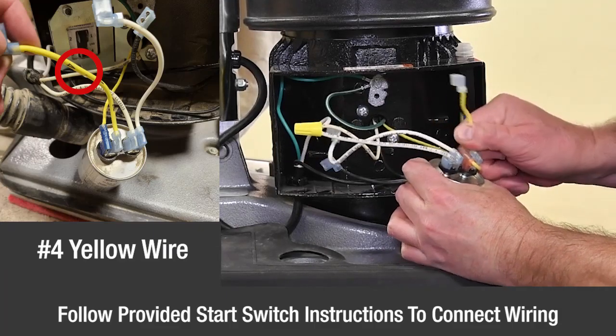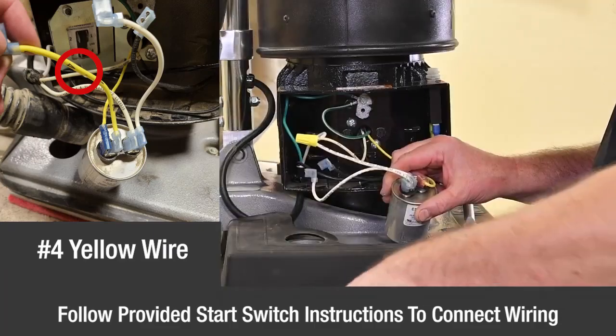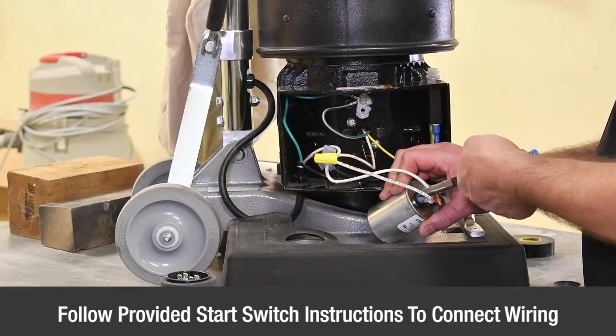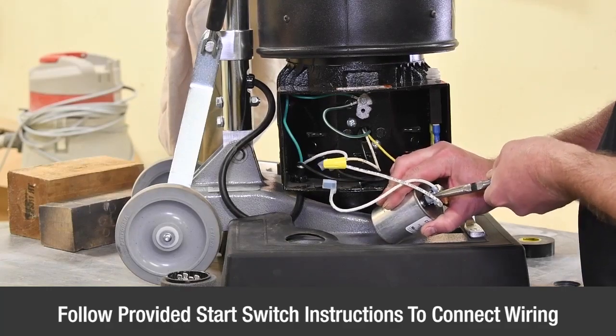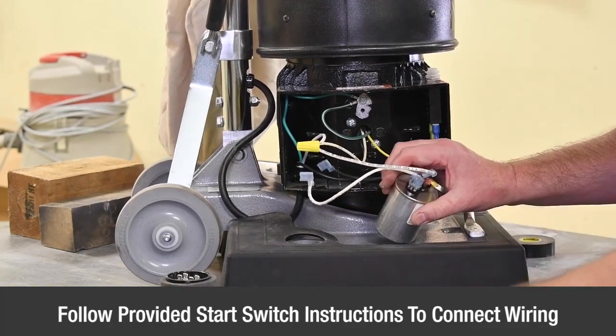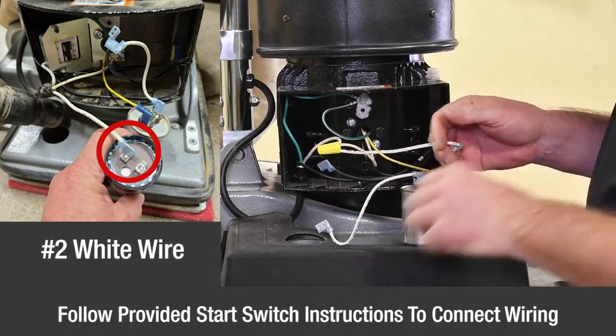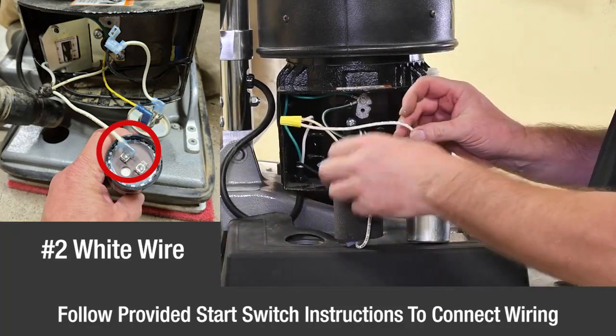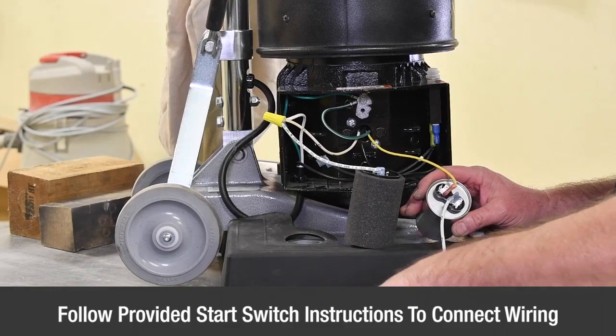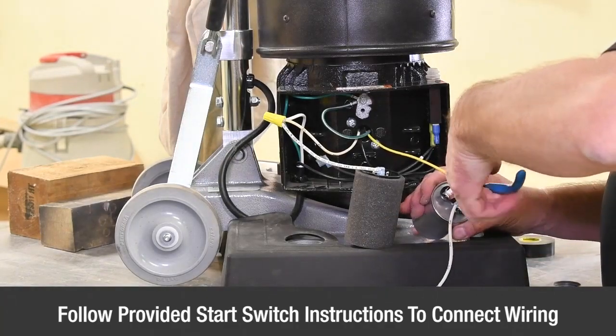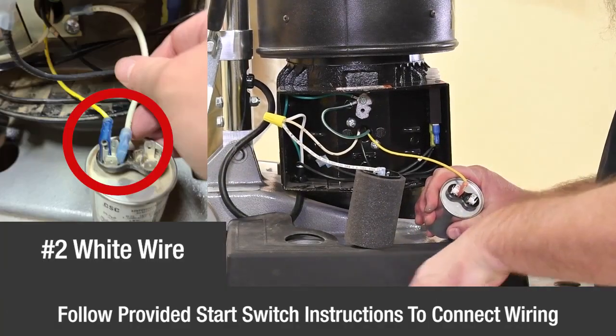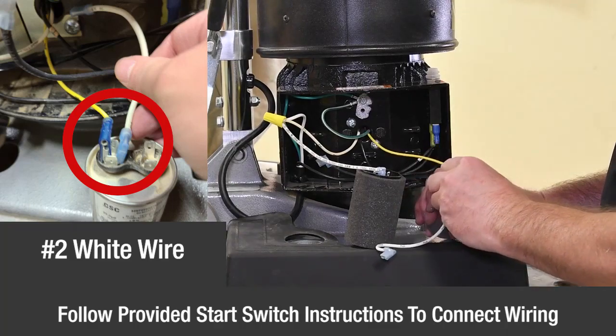Remove the number 4 yellow jumper wire between the start switch and start capacitor. Disconnect the number 2 white wire that goes to the wire nut from the run capacitor. Connect this number 2 white wire lead to the new start capacitor. Move the number 2 white jumper wire on the run capacitor to the other side of the run capacitor with the number 4 yellow wire to the motor.